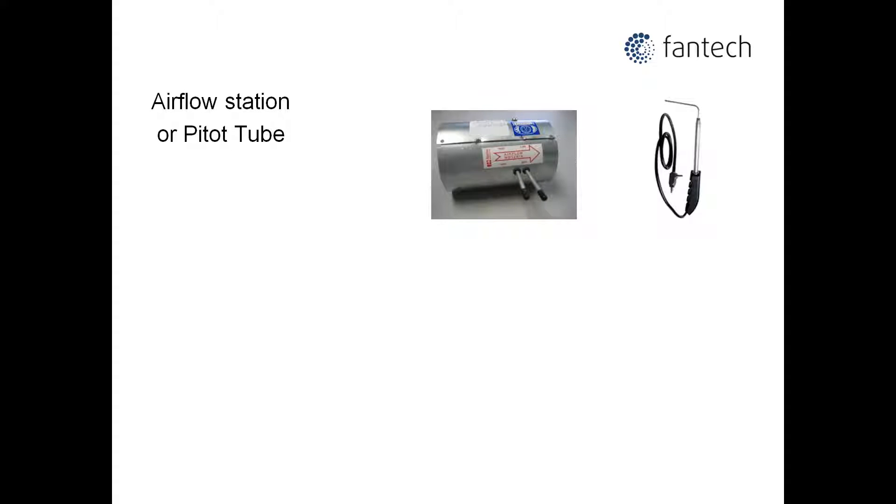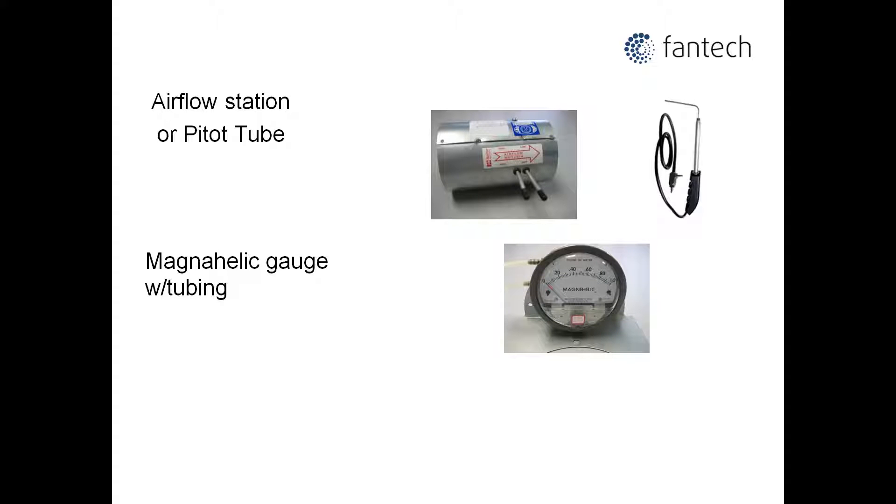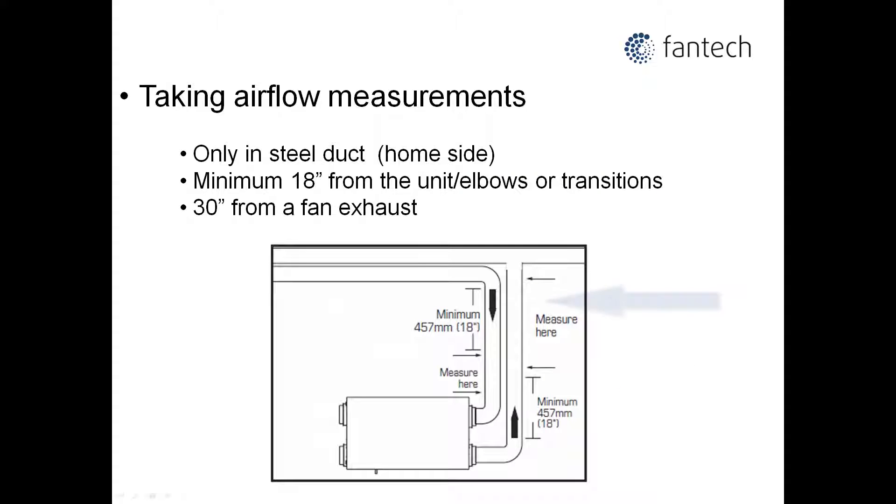Two common methods of balancing air flows and pressures are airflow station and pitot tube. Both these items require the use of a Magnehelic gauge, and of course a selection of hand tools, tape and masking.